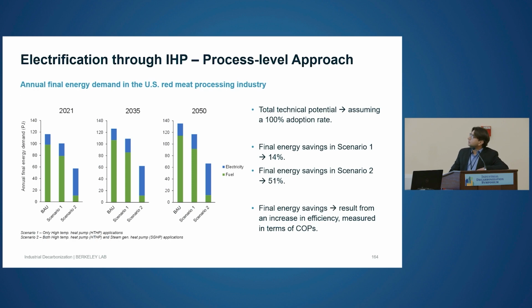And here are the results. For energy savings, but before that, you can notice that there are a couple of scenarios, scenario 1 and 2. Scenario 1 is where we are only looking into hot water production, because heat pumps have been existing for quite some time now. The technology for delivering temperatures below 100 degrees is somewhat matured, while the ones delivering higher temperatures of steam, like over 120 or 150, are in the early stage of commercial deployment. So that's scenario 2. We wanted to make this distinction and see how much impact the current, more established technology can make, and what is the potential for these technologies that are getting matured, I mean the current state of the art.